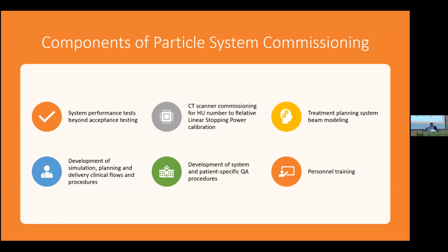So there's all these three phases, and we need equipment to be able to do this. We can't just show up and look at it and say, oh, it looks good, right? We need tools to be able to do this properly. And during the technical commissioning portion, this is part of it when you're also talking with the vendor and such. There's certain tools that they may need only one time, but you need a lot. So maybe the hospital is the one buying that particular system, and the vendor will use it for a month or two, and then you're going to use it the next 20 years kind of thing, or vice versa. There's something you only need maybe one time during the acceptance that you don't necessarily want to go purchase for whatever it is. You're only going to use it one time during acceptance. So maybe it's something the vendor has, and you negotiate that you're going to use their tool in a certain way to do the test. So just things to kind of think about.